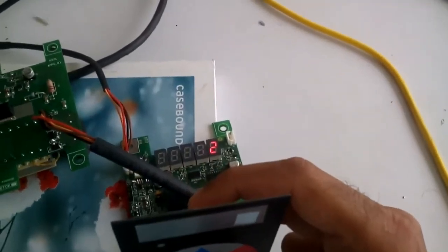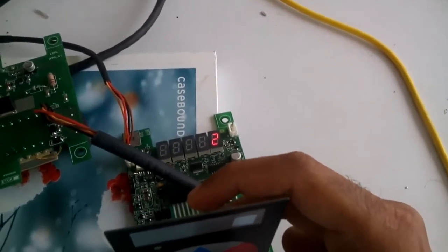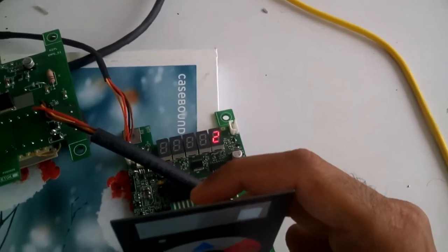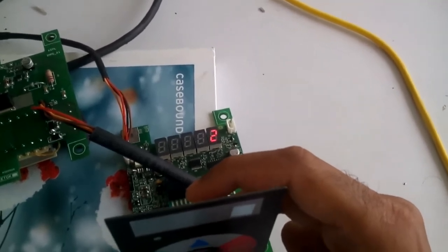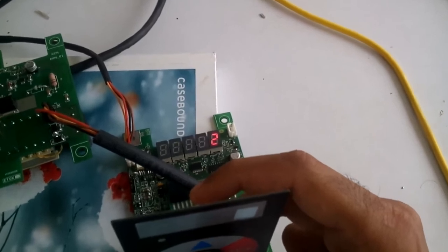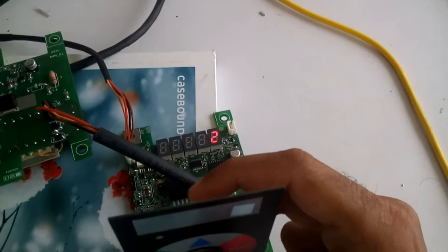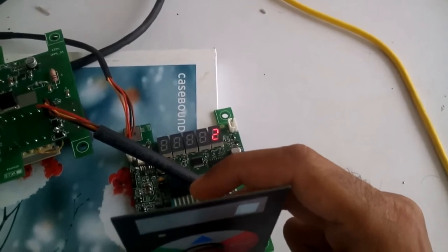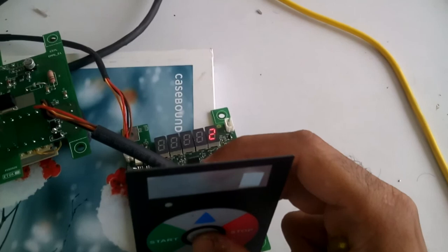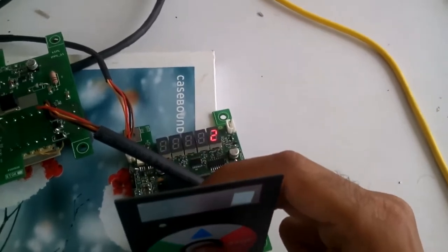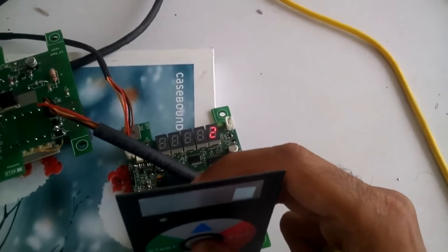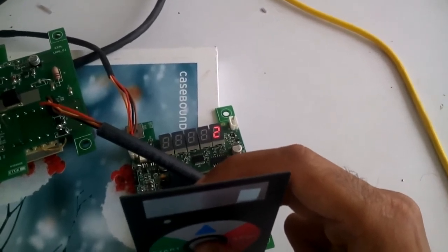Now if the drive comes in for maintenance and the engineer wants to check whether the self-test has been done or not, you can see this parameter. If it is 2, it's done. Now let's say the maintenance has been done on the drive and the self-test has to be reinitiated. This is also possible, because this parameter can also be set to 1. If you set it to 1, then the self-test begins again and it will self-test the drive again.